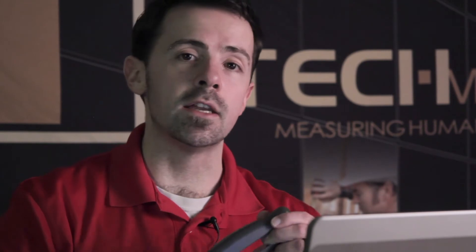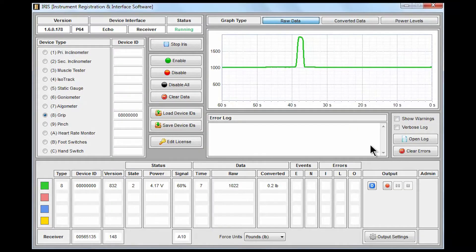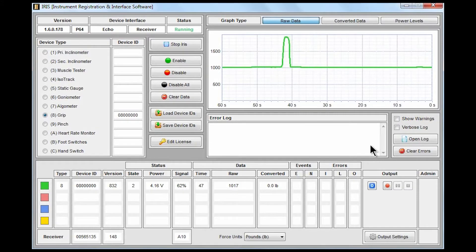For today's demonstration I'm going to be using a JTEC grip strength gauge. You may have seen it in other capacities before, a standard five position grip strength unit. And you'll also need a receiver of some sort, in this case one of our USB freedom receivers. It is able to establish connections to up to four devices simultaneously.